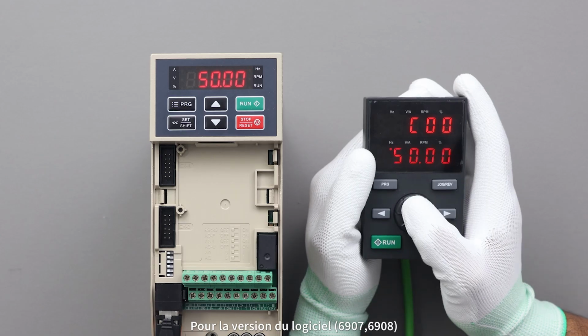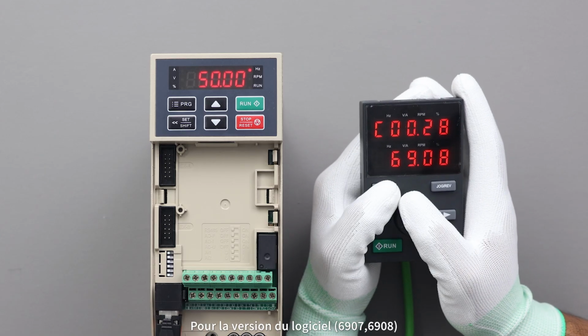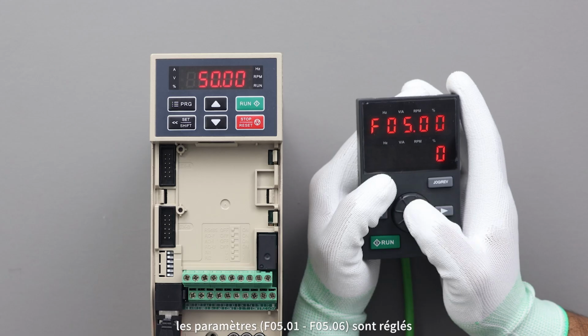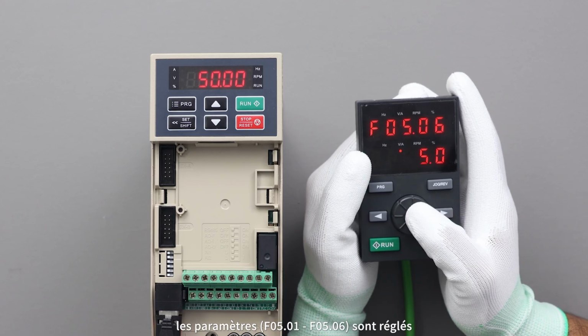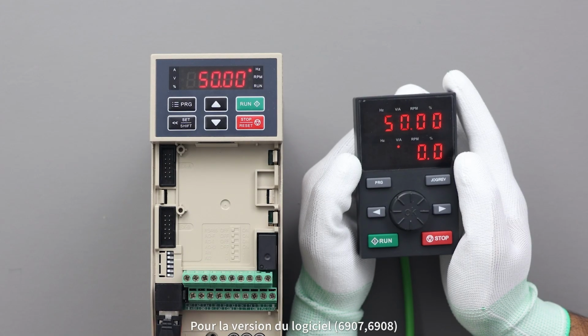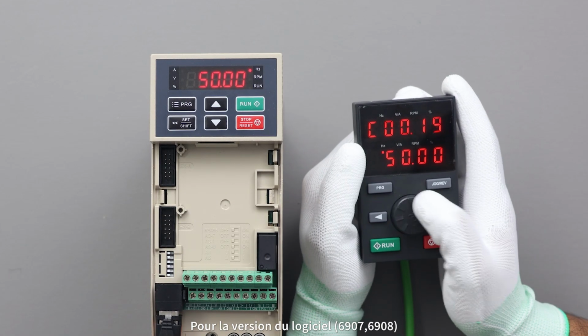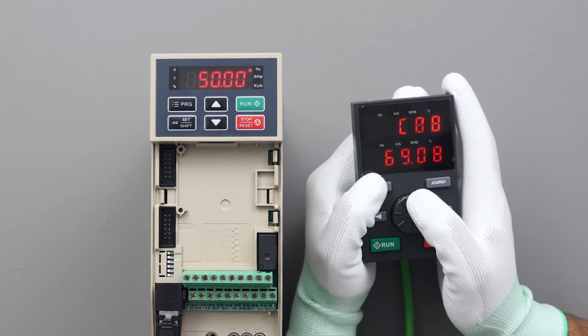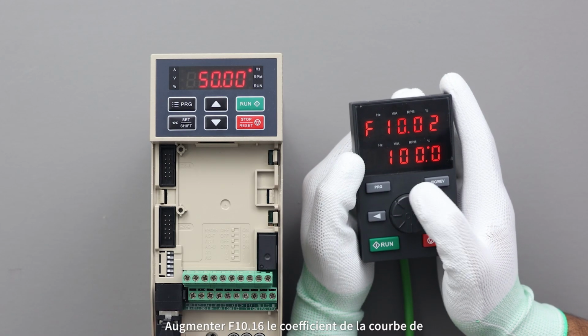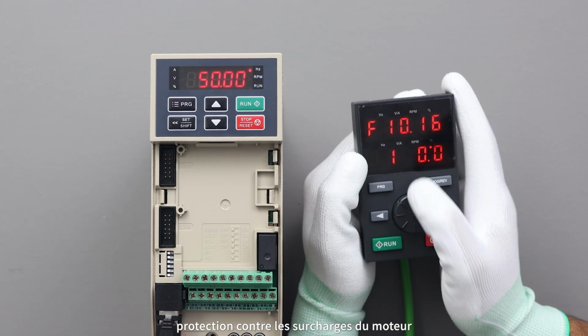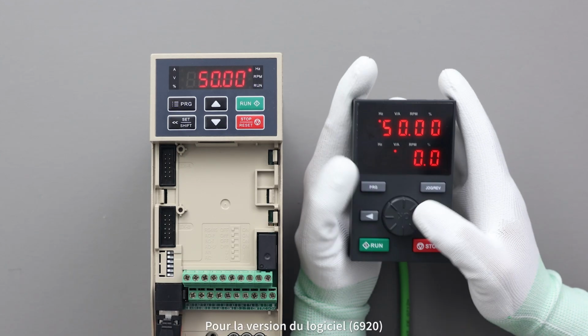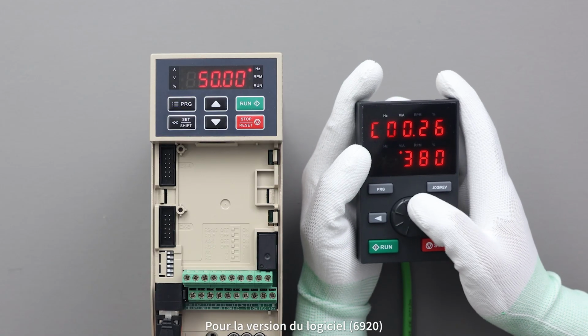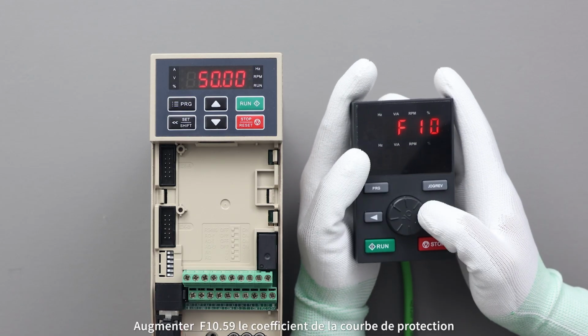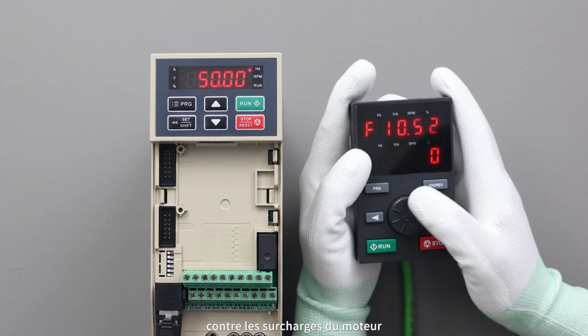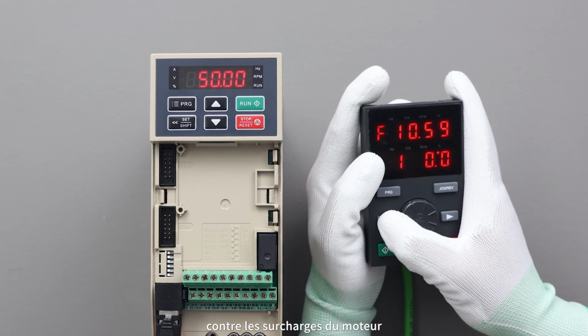For software version 6907 and 6908, set F05.01 to F05.06 parameters. Overload protection adjustment. For software version 6907 and 6908, increase the F10.16 motor overload protection curve coefficient. For software version 6920, increase the F10.59 motor overload protection curve coefficient.